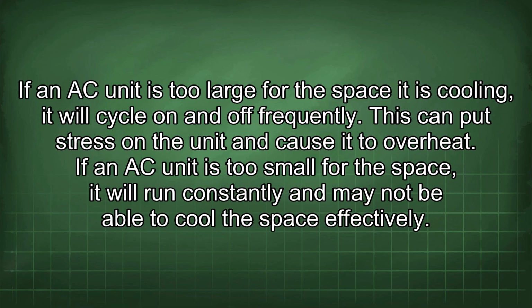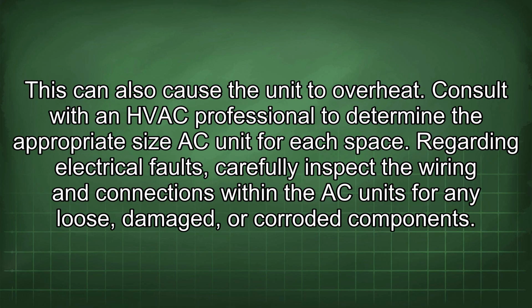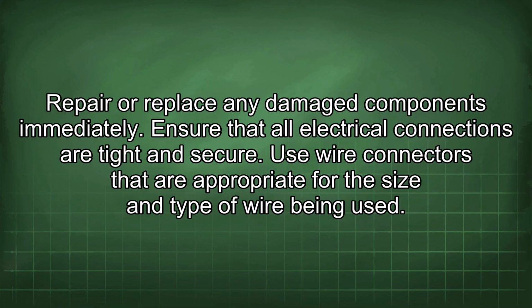If an AC unit is too small for the space, it will run constantly and may not be able to cool the space effectively. This can also cause the unit to overheat. Consult with an HVAC professional to determine the appropriate size AC unit for each space. Regarding electrical faults, carefully inspect the wiring and connections within the AC units for any loose, damaged, or corroded components. Repair or replace any damaged components immediately. Ensure that all electrical connections are tight and secure. Use wire connectors that are appropriate for the size and type of wire being used.